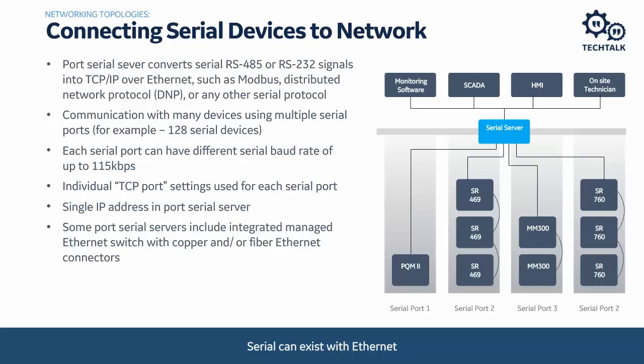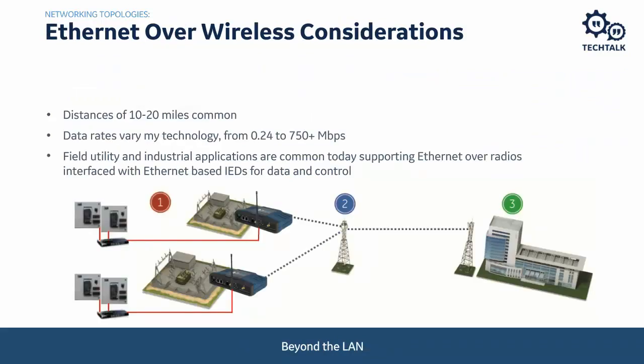Most of today's discussion has been focused on substation communication within the substation — the local area network. There is a need to expand the network beyond the substation for remote applications such as SCADA, energy management, remedial action schemes, and phasor measurement units. However, there will be limitations in the infrastructure we can install due to budget constraints — the cost of running fiber from point A to point B may not be economical, or the terrain might prevent it. We might need to go over a river or mountains where we can't run fiber.